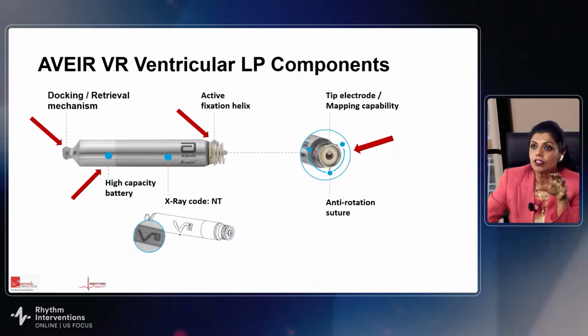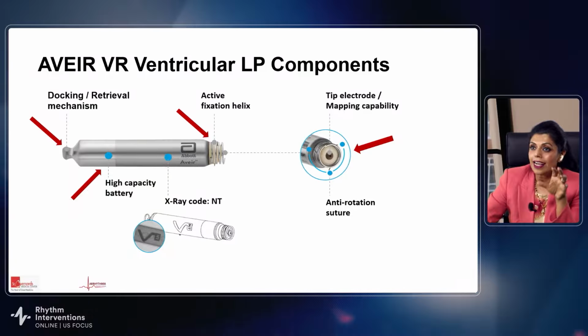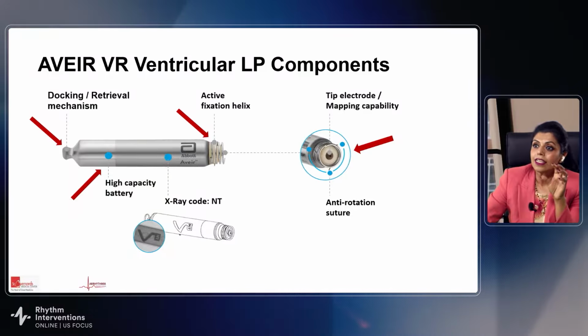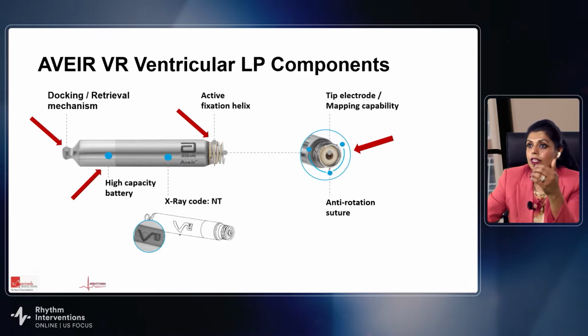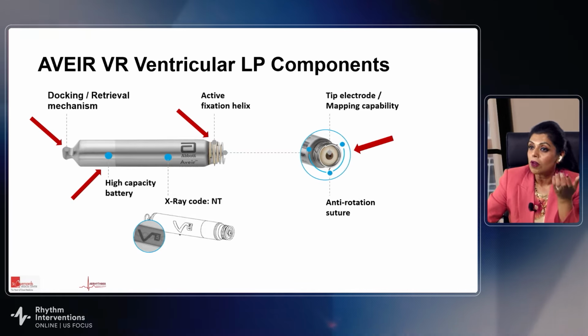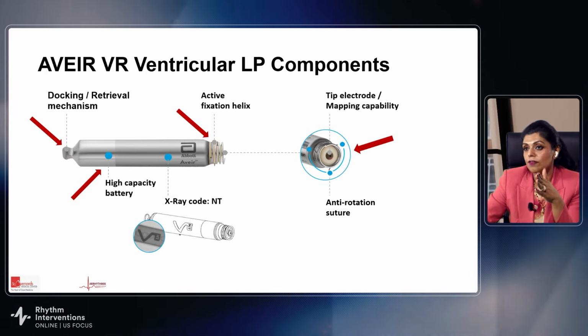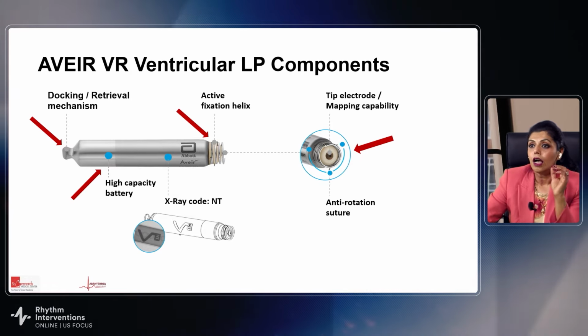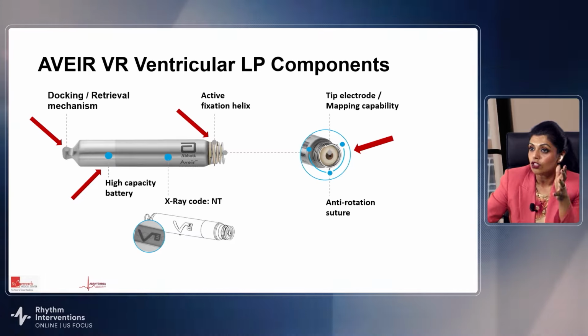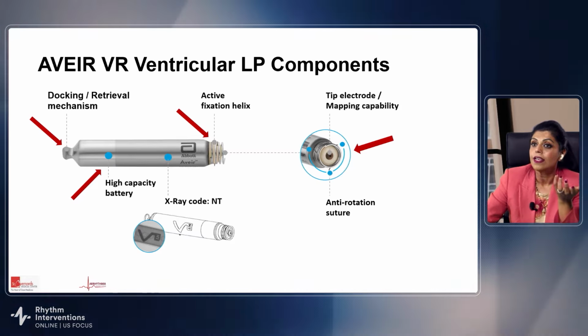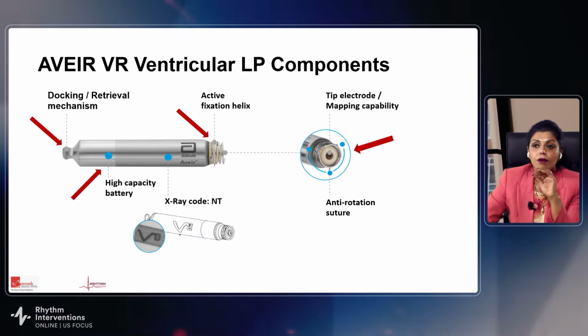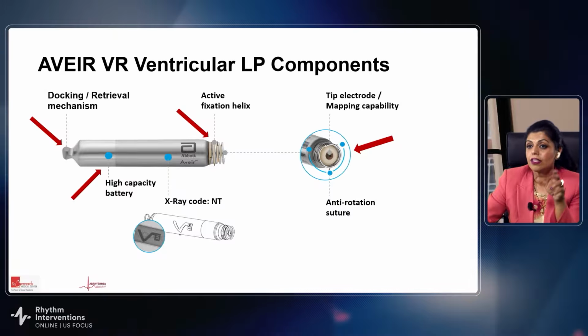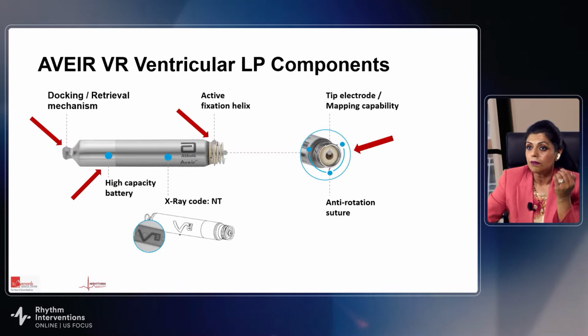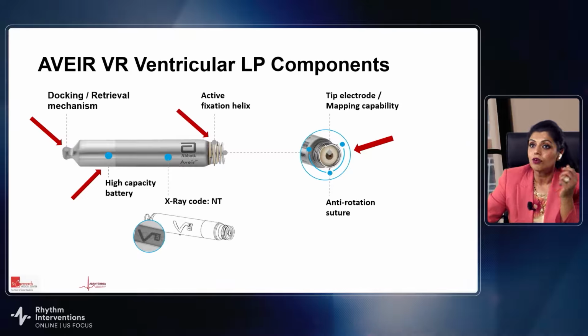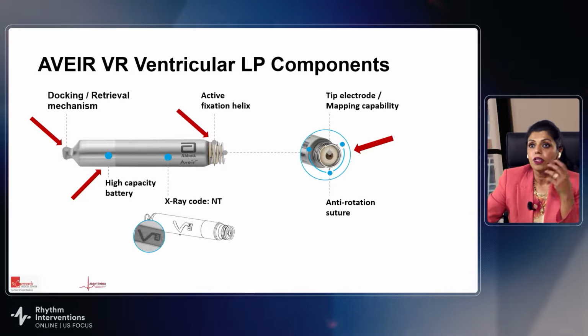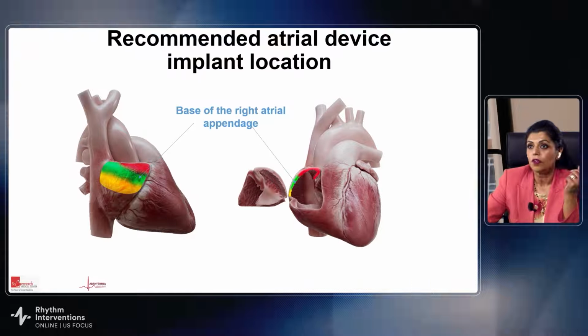You can see the ventricular device, again, has an active fixation helix, but the cathode is at the tip. It sits mounted and allows for pre-mapping. Both the atrial device and the ventricular device allow for pre-mapping. Both of the helixes have anti-rotation sutures, so it also gives stability to the device. Both devices have a high-capacity battery. The ventricular device has a bigger battery. It's a longer device and also has that docking button that allows for implant as well as retrieval.